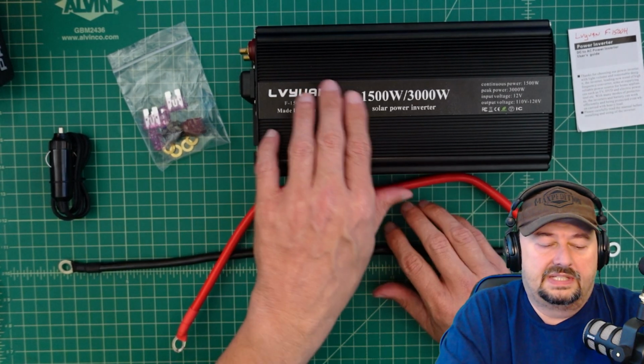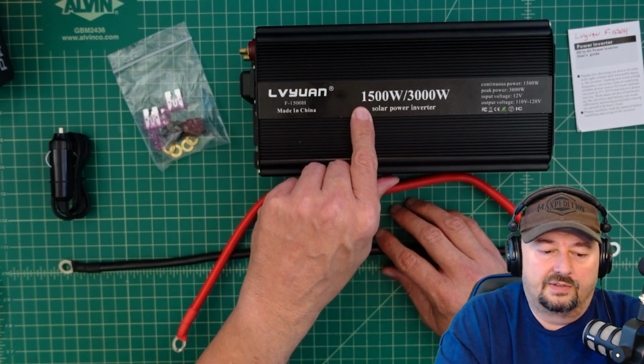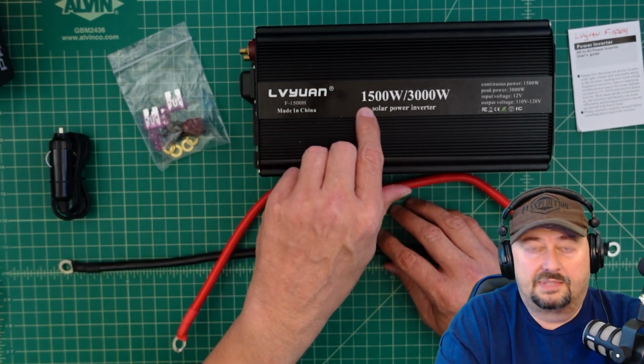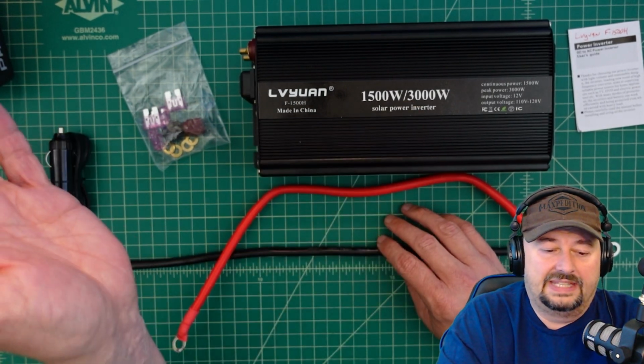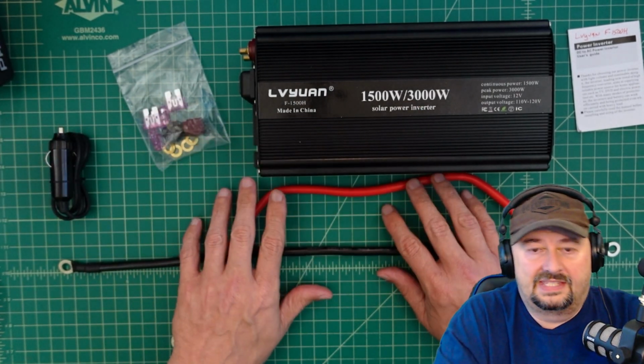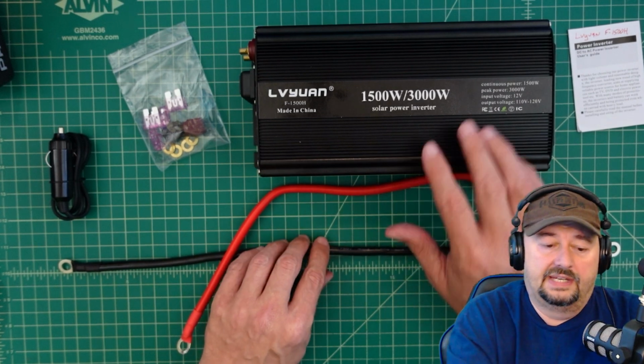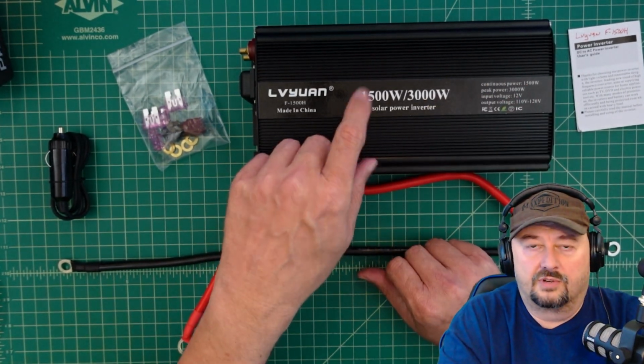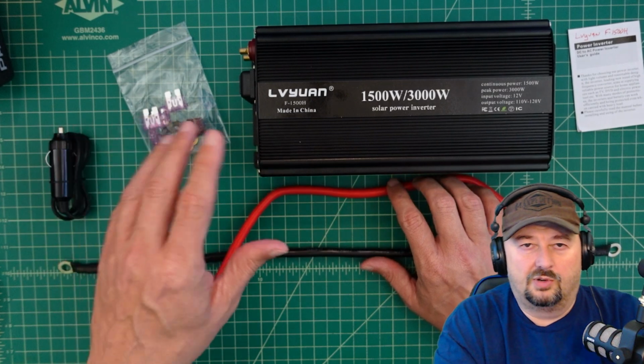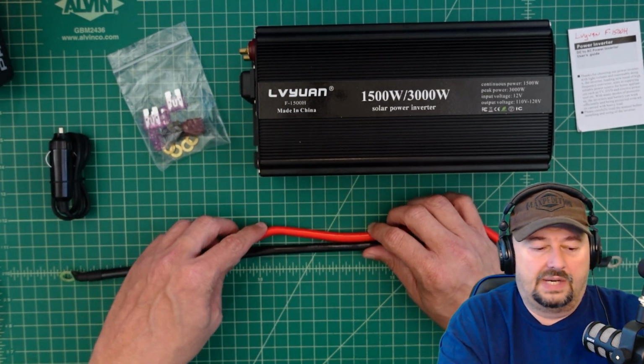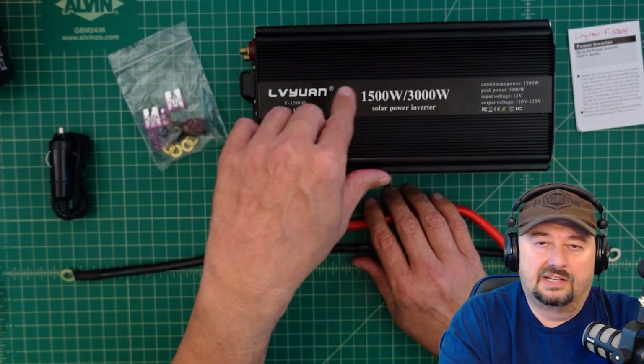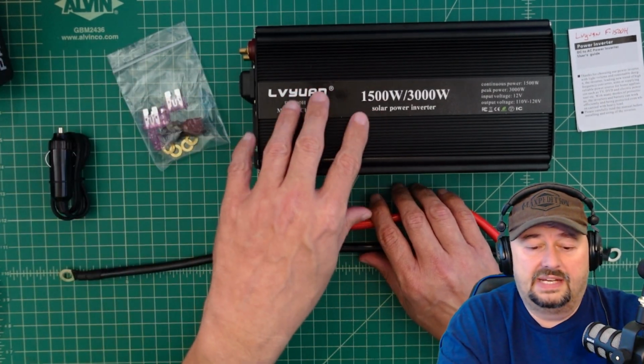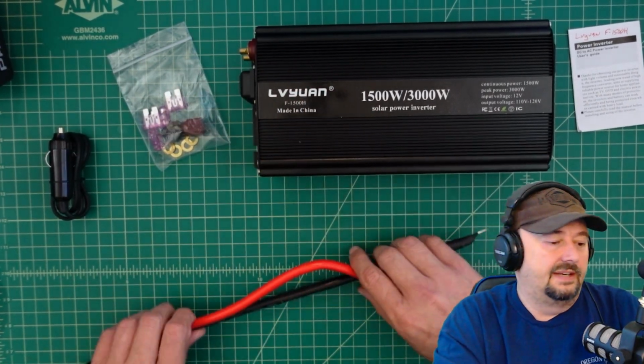What I would tell you is that when you're starting to look at 1500 watts, it's around 125 amps. If you went up to 3000, I think it's 250 amps. This is probably not adequate for 3000 watts, and I wouldn't use it for 1500, but that's very typical of these inverters, is that you would get wire like this. If you're going to run this at a lower power, maybe 750 watts, you may not have a problem, but we'll test all that out.